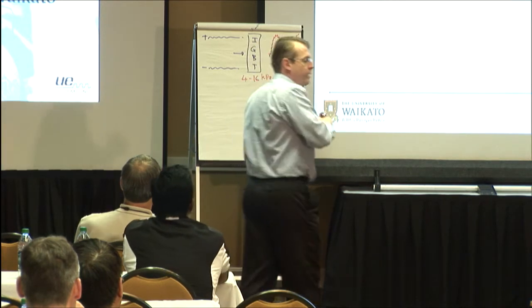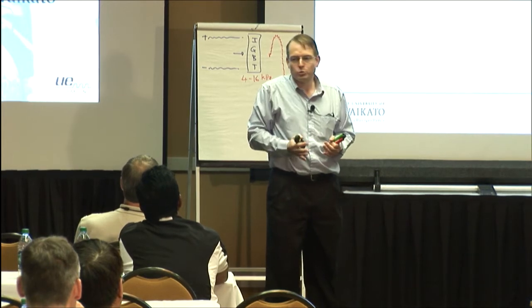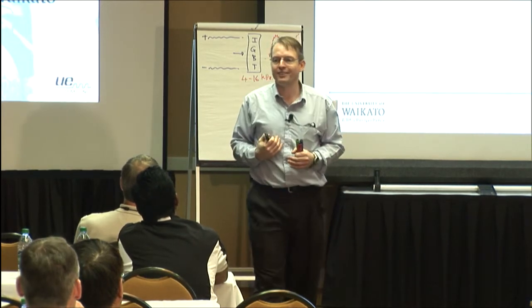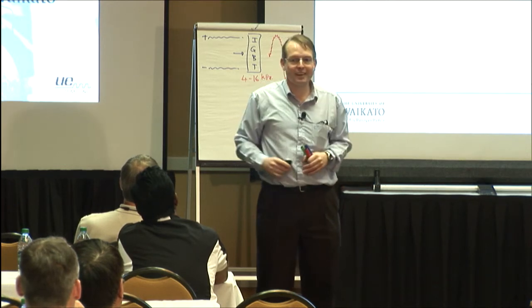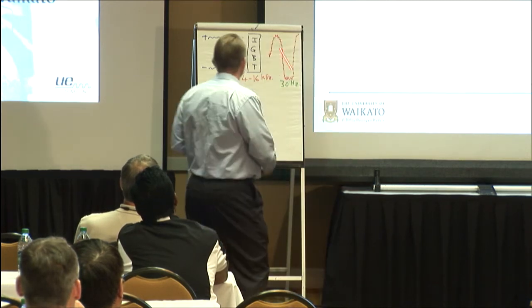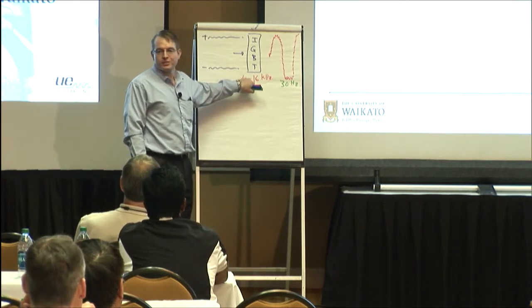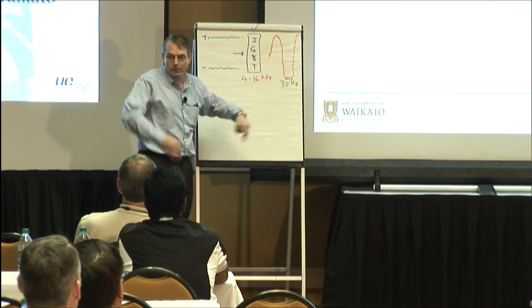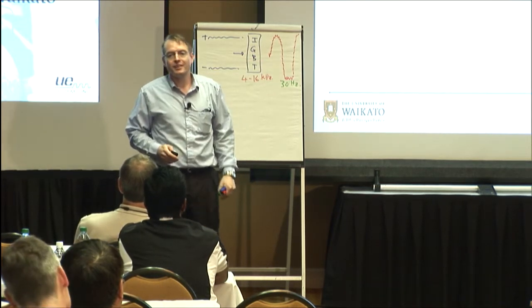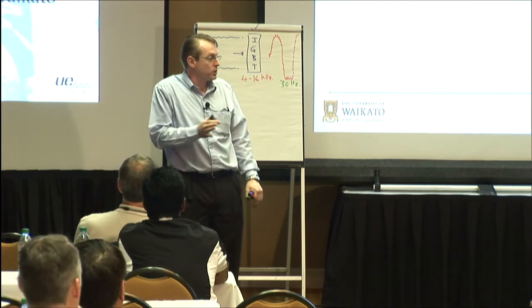I used to work for a company that built VSDs, and you want to know what my job was? I was responsible for dumping that power. Because where did that power go? Heat. Okay. What drives that power? The higher this frequency, the bigger the losses, because the losses are all generated here. The higher you switch those things, the bigger the losses. Okay. But in the grand scheme of things, that can still be a penalty worth paying, right?